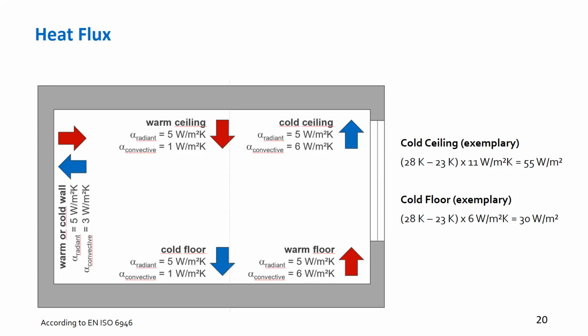When talking about how to heat and how to cool with radiative surfaces or with building surfaces, we know that we have to look at the factors for heat transmission at the surface. And we know that radiant heat flux is indifferent to the orientation. It's always 5 watt per square meter and Kelvin or something like this. And that the convective part is very much differing from the question if the air stays on this level or if the air is moving away from this level. So heating with the floor will be done at a number of 11 watt per square meter and Kelvin. Cooling at the ceiling the same, and if you tilt it, cooling with the floor is much, not less effective, but you need a higher temperature difference between the room and the floor to get the same heat flux.